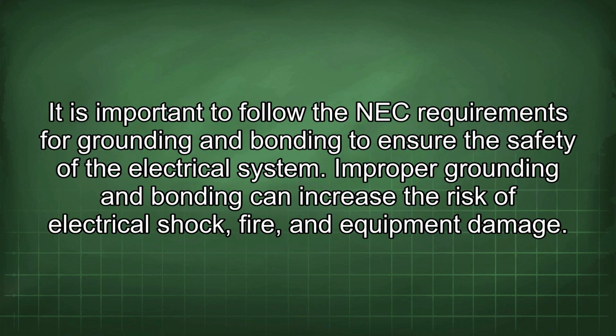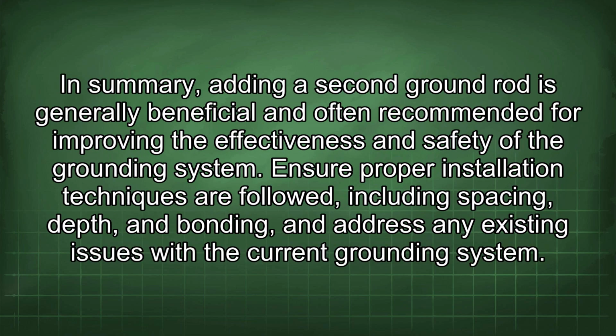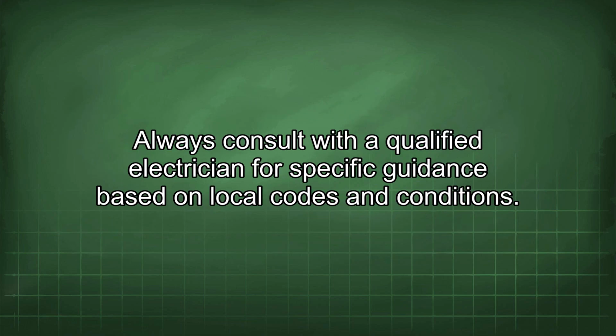It is important to follow the NEC requirements for grounding and bonding to ensure the safety of the electrical system. Improper grounding and bonding can increase the risk of electrical shock, fire, and equipment damage. In summary, adding a second ground rod is generally beneficial and often recommended for improving the effectiveness and safety of the grounding system. Ensure proper installation techniques are followed, including spacing, depth, and bonding, and address any existing issues with the current grounding system. Always consult with a qualified electrician for specific guidance based on local codes and conditions.